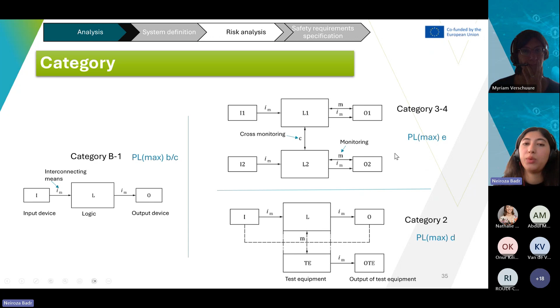Another piece of information you need to know is that in category B, the maximum achievable performance level is B. For category 1, the maximum achievable performance level is C. For category 2, the maximum PL achievable is PL D. For category 3 and 4, the maximum PL achievable is PL E. So what you need to understand is that the more effort you put into your architecture design, the more reliable the category you have in your architecture, which helps on the PL level.